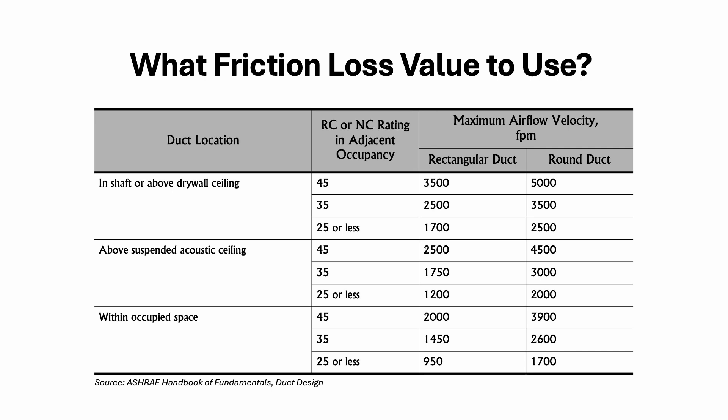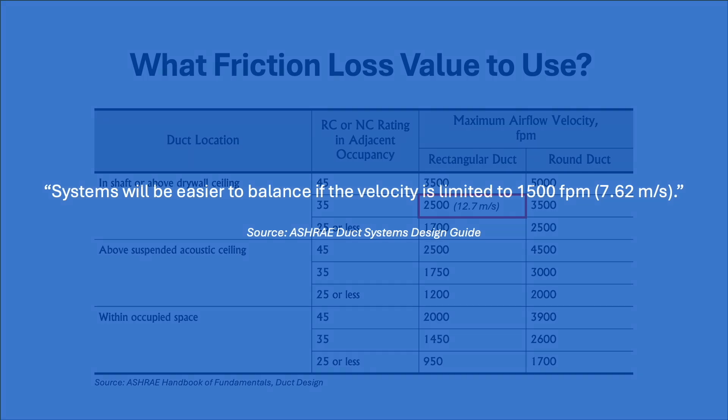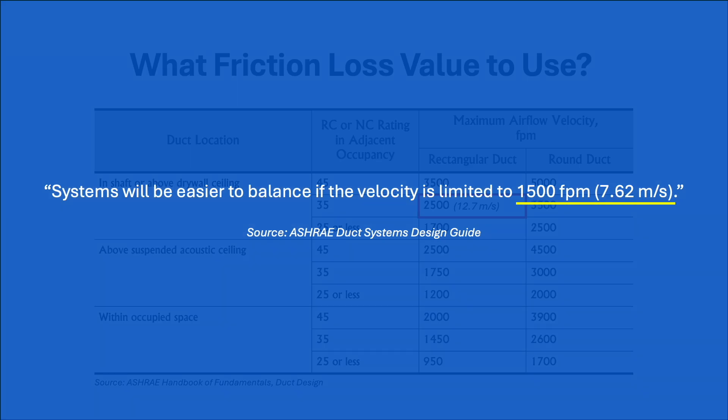If our duct will be installed above the ceiling, then we can use 2500 feet per minute if we are using rectangular duct. However, we might want to keep the velocity below 1500 feet per minute for easy air balancing.